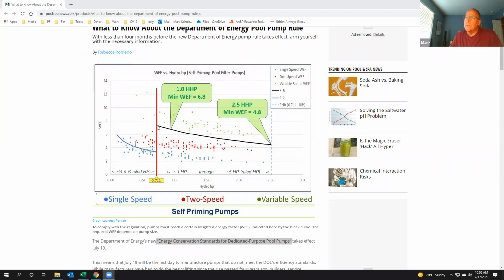For this, you see a demarcation at 0.711 hydraulic horsepower. Anything below that has a different requirement curve than anything above it. I think you've seen on different websites that anything below 0.711 is fine. Well, that's not exactly true. There's still a requirement. You can still see some single speed pumps will be below that level, and so they will not be compliant.